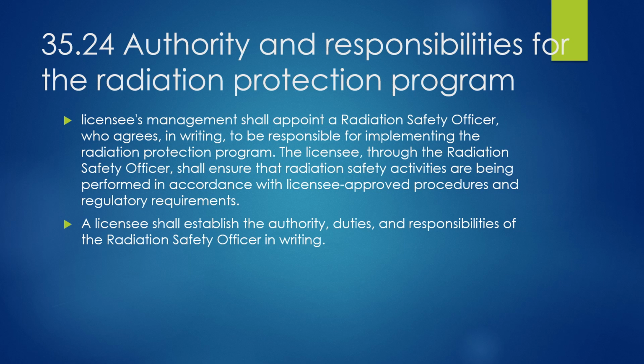So 35.24 is the authority and responsibilities for radiation protection programs. And it really just says that licensees shall appoint a radiation safety officer. That radiation safety officer has to be qualified and approved. They also have to agree in writing to be responsible for implementing the program. And then the radiation safety officer has to ensure that the radiation safety activities are being performed in accordance with the regulatory requirements. So that's really just saying the RSO is the person that's in charge of everything and responsible for just the overall use of the license and the oversight, making sure that there's regulatory compliance. And that person has to agree in writing to say that they're willing to do that.